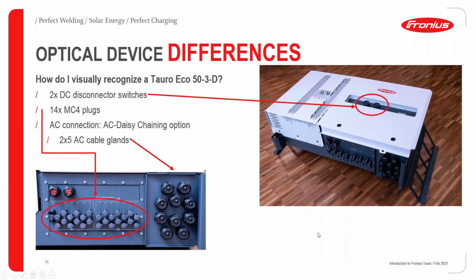How do you differentiate a D version? By seeing it. If you look at the picture, the left side picture is the bottom of the inverter, and on the right side you can see the full inverter. So you can see 2 DC disconnector switches in the D version, and then there are 14. It's a 50 kilowatt Tauro Eco inverter, so you have 14 MC4 connections, like MC4 plugs for 14 strings. And then on the right side of the bottom, in the left picture, you can see there are options for 2 times 5 AC cables, which means if you are ordering for a project and you need AC chaining, if you are going to connect the inverters on the AC side and bring just one cable from the inverter to the LT panel, then you have to mention it beforehand, so that you will get space with the AC cable glands for 2 times 5 ACs.